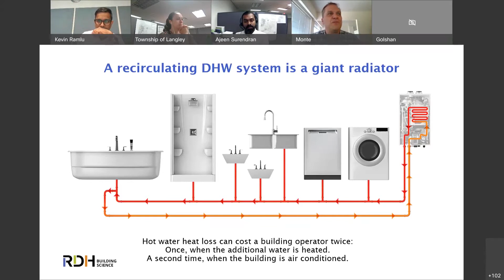Remember this is a particularly painful loss for the building operator. Hot water heat loss costs a building twice: once you pay at the boiler or heat pump to create the hot water, and then you pay again at the air conditioner to cool the building because you heated it up with your hot water. So every bit of this hits you twice.